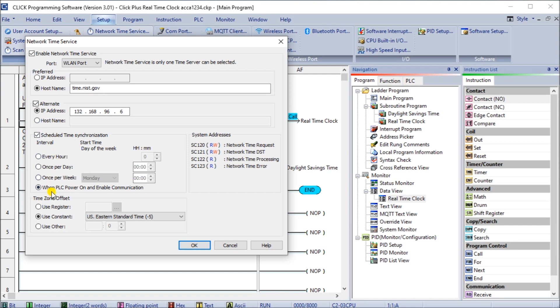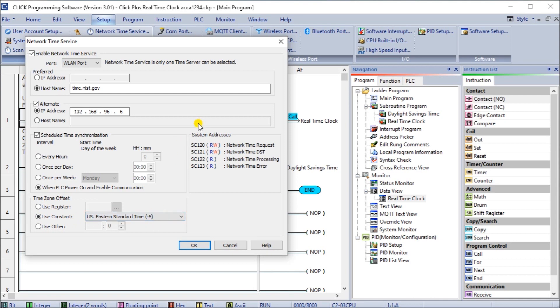Then we do a synchronized time so when the PLC powers up and enables communication, it automatically will pull and update the time to the correct time. Then we have our time zone offset so we're using the US Eastern standard, so it's minus five hours.